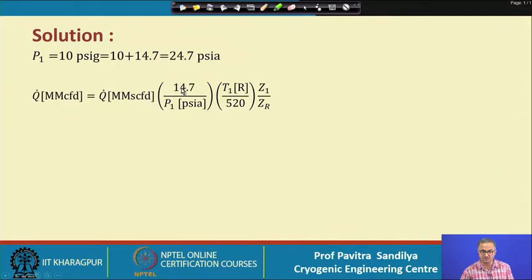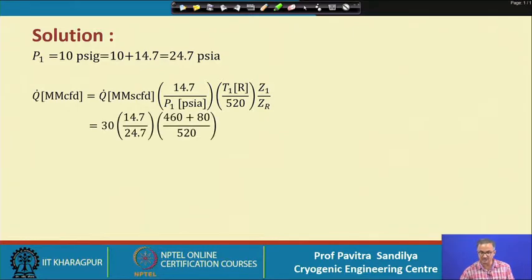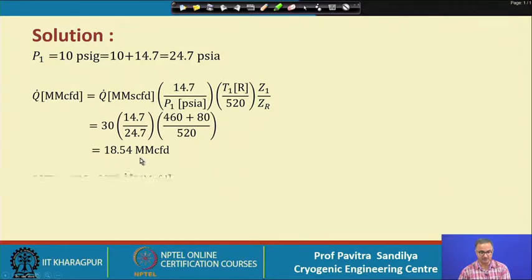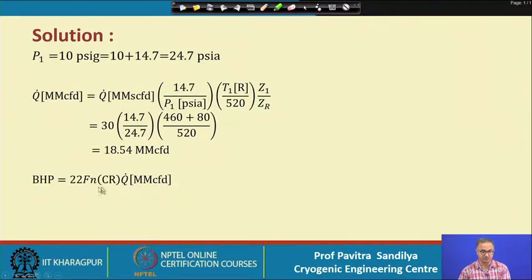Here, 14.7 and 520 represent the standard conditions, and we assume Z1 equals Zr. With this assumption, we plug in the values — the temperature is converted from Fahrenheit to Rankine by adding 460 — to obtain the actual volumetric flow rate of the gas.